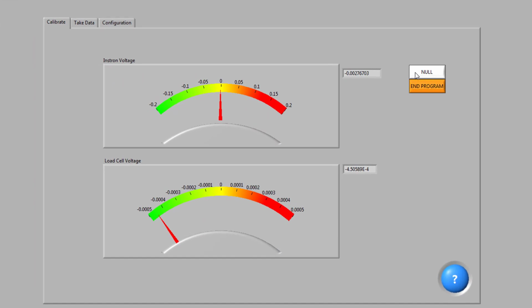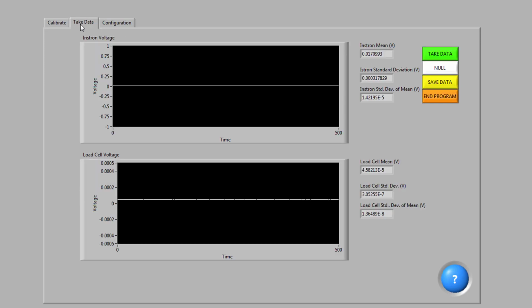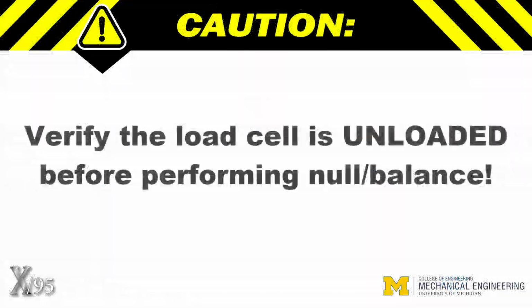In LabVIEW, click the Null button to zero the S-type load cell. The needle of the lower meter should move to 0. Now navigate to the Take Data panel, where you'll see another null button, which performs the same operation. You should periodically null both load cells. Always verify the load cells are unloaded when balancing.